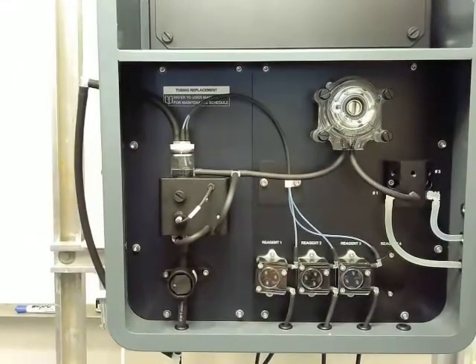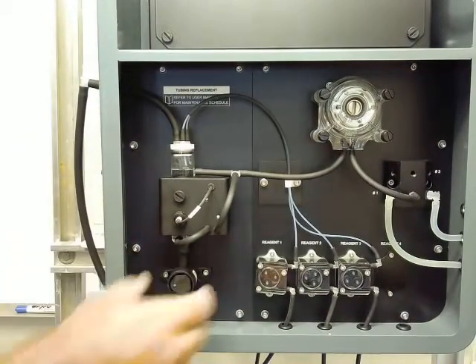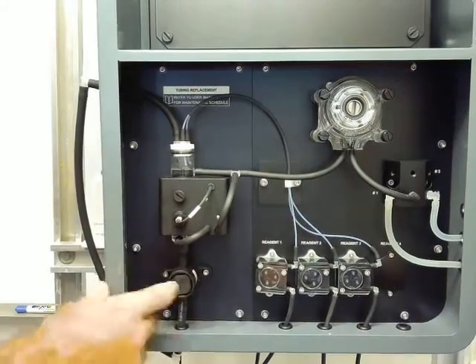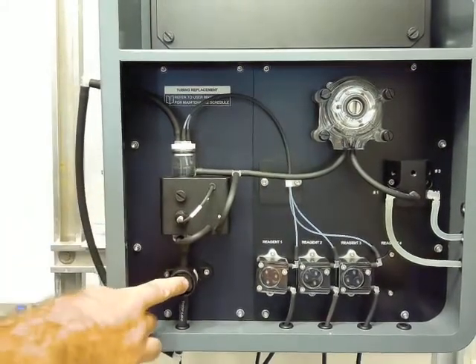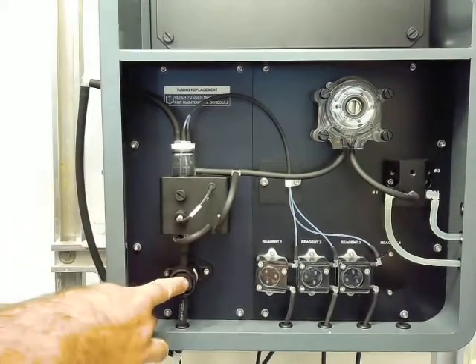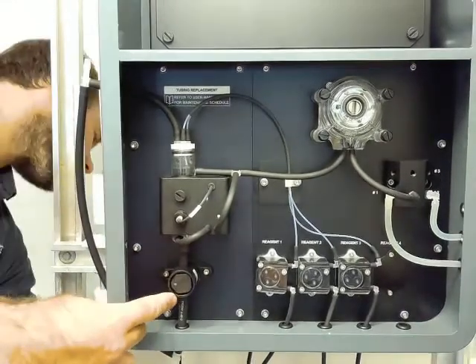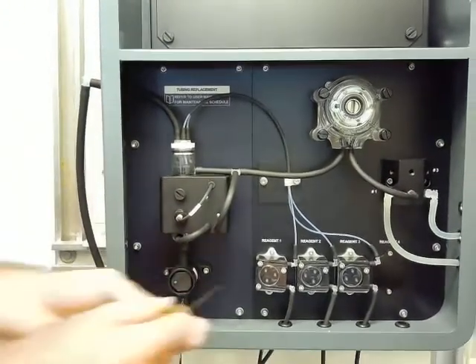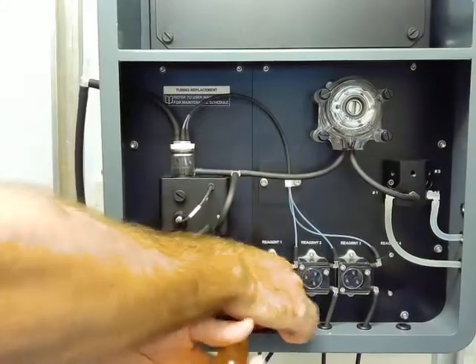All right, so in order to gain access to this flow cell block, I'm going to basically take this panel out of place. First thing I want to do, I just want to drain any sample that's in the flow cell, just so it doesn't leak all over me. And then there's 6 screws in the plate that we can remove.